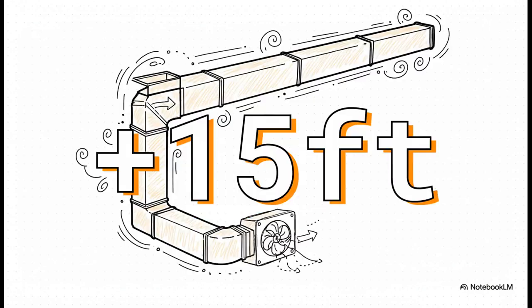So how much of a difference are we really talking about? Is it a big deal? Get this. A single standard 90-degree turn can add the equivalent of 15 feet of straight duct. Just think about that for a second. One little elbow makes the fan work as hard as if it were pushing that air another 15 feet. Now imagine a whole system with, I don't know, a dozen of those turns. That resistance, man, it adds up so fast.